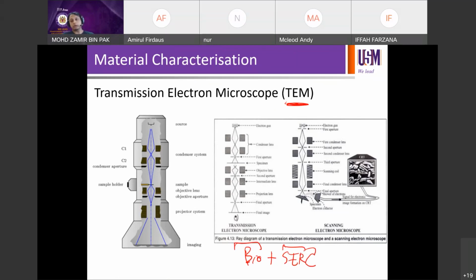So it looks similar to SEM, but it is more complicated in terms of the configuration, the way it works, and sample preparation. It's harder to do. It also uses an electron beam, and then you have a condenser system in the middle, and then a condenser aperture, a sample holder in between, a couple of lenses, a projection system, and then the imaging will be at the back.